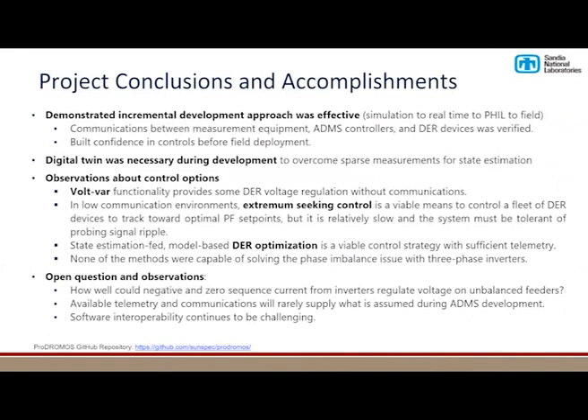The communications between each of these elements is a major hurdle and takes quite a long time to debug, but we could verify that through this process, and it built our confidence that it would work in the live demonstration. The digital twin was necessary to get over the limitations of our state estimation system because it was too sparse without those simulated PMUs. And Volt-var did well. We didn't have it too aggressive, but it did improve voltage regulation, especially on the PNM system.